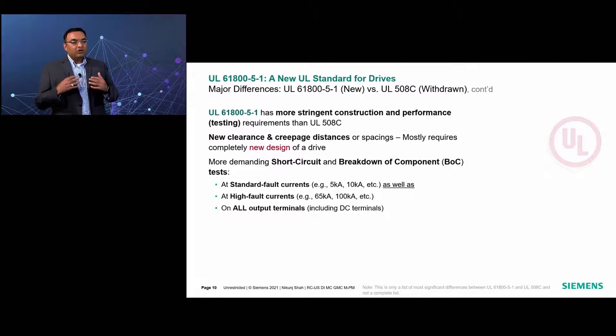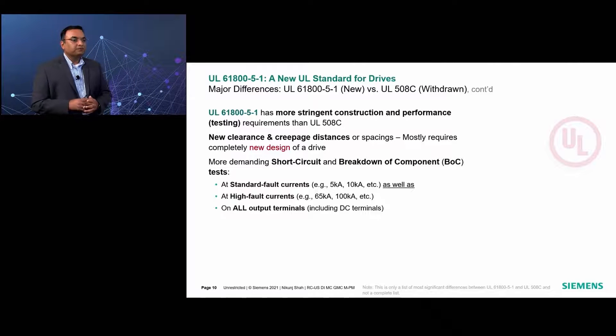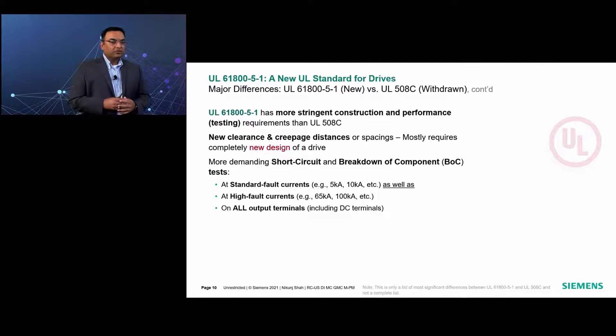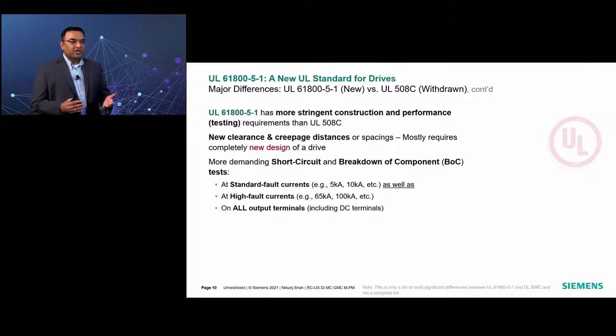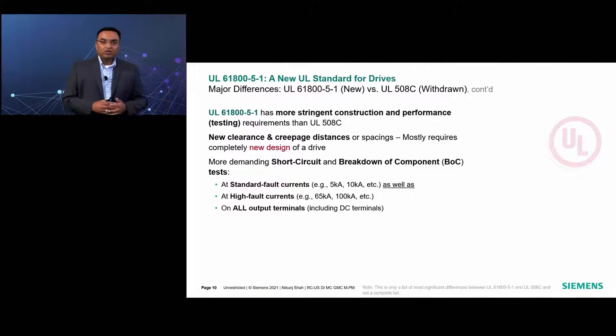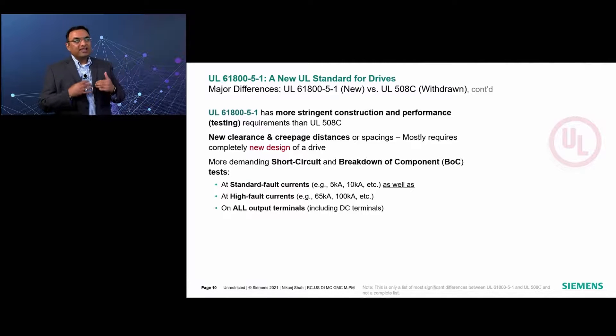Similar to the short circuit test, the breakdown of component (BOC) tests are also performed at the standard fault current level of 5 or 10 kilo amps, as well as at the high fault current levels of 65 or 100 kilo amps, according to this new standard. The BOC test is one in which components within the drive that pose a risk of shock or fire when they fail — either short or open — are identified. Components such as DC bus capacitors, IGBTs, MOSFETs, or diodes are examples. Once identified, the component breakdown is simulated in the lab while the drive is running at full load conditions.